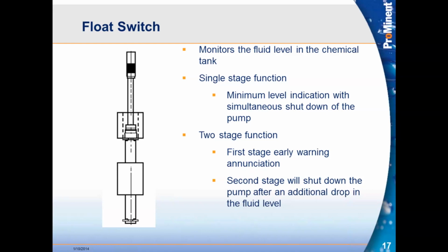Above that molded part, you see just a little weight, so it's going to help it keep towards the bottom of the tank. Because remember, we do have a float there. We want that to float in that fluid so that we know when it goes below there, it's going to lower and hit that stage on that particular switch.